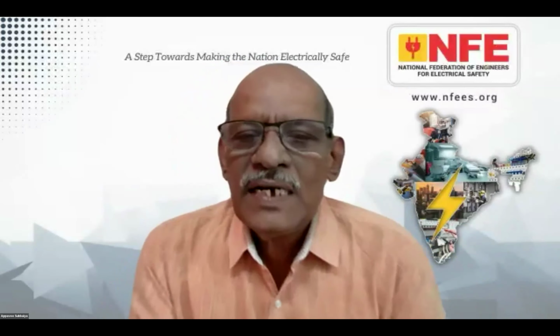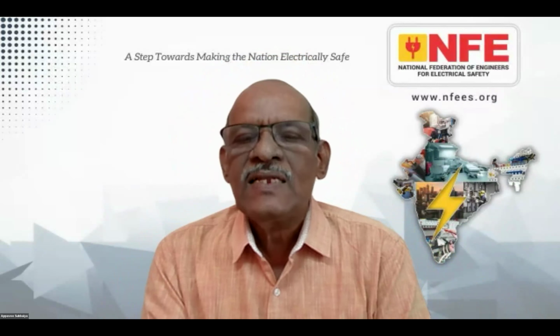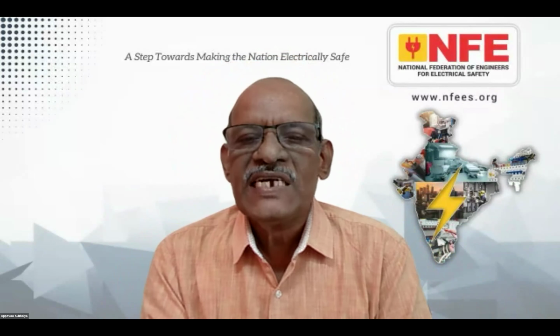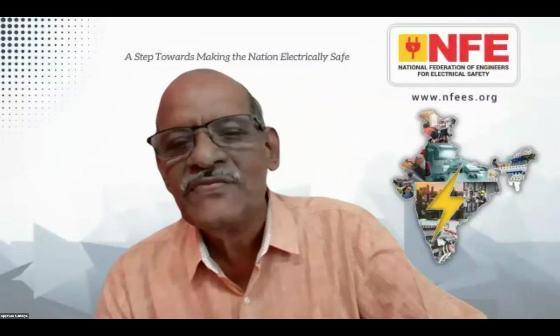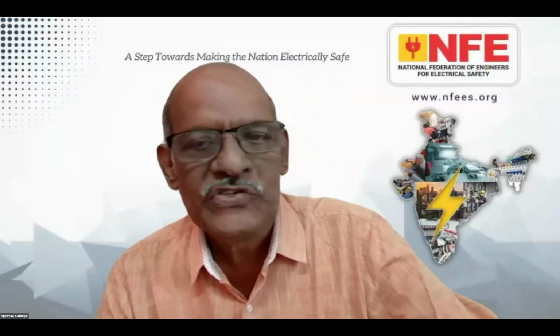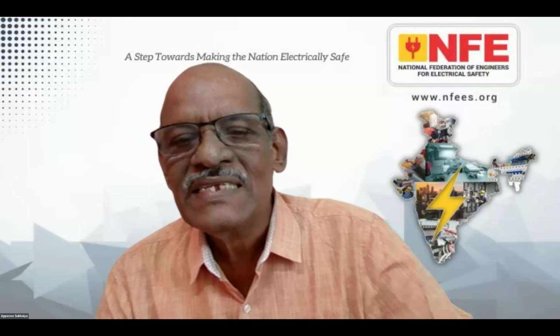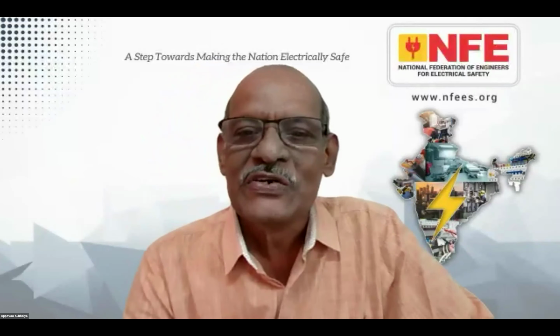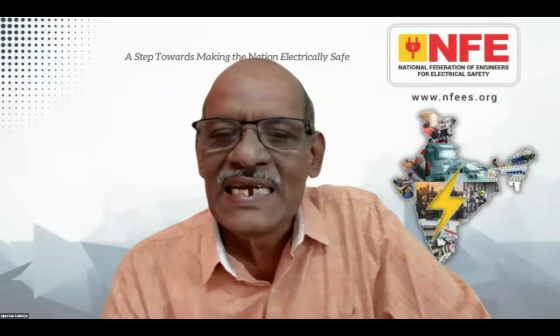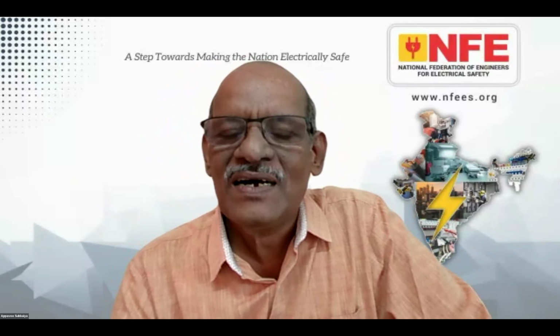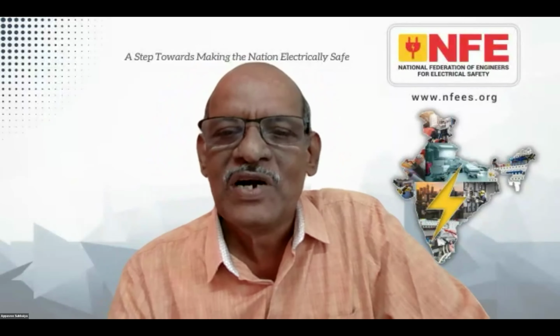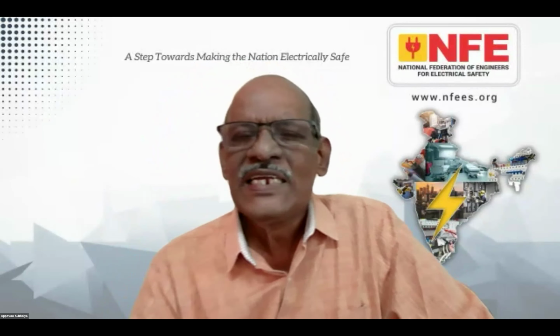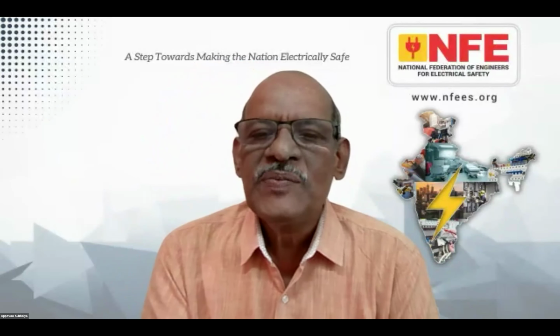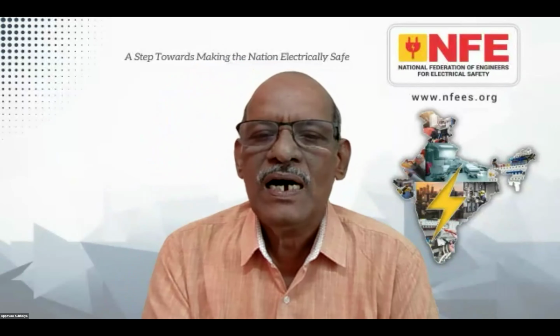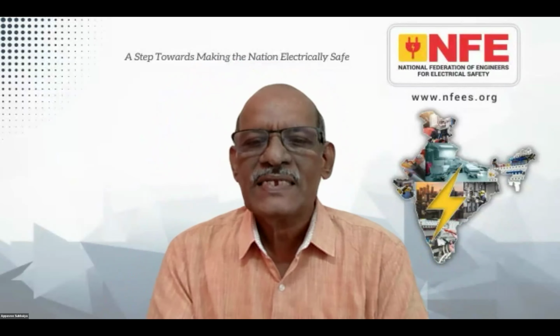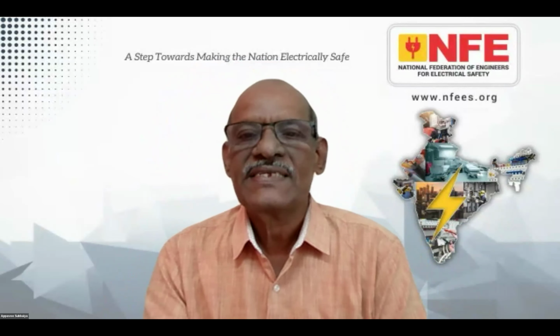Sir, it's a very good subject. It should be dealt with in detail. Regulation 18 is there that we have discussed along with Manu Varkey. It is there in our country for the past 100 years, but it is still missing, elusive, whether the consumer is ready to connect his PE conductor to the earth neutral of the supplier, or whether the supplier can segregate his earthing system, neutral earthing, body earthing from the substation. So these are very typical areas, and we already had some webinars on this. We will have a webinar on this specific issue, how to address it in a practical manner, depending upon the conditions.